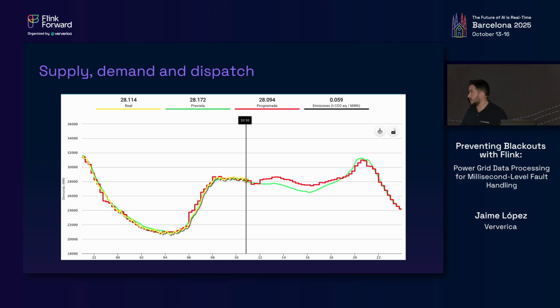When demand spikes, we wake up in the morning, you see it around 6 a.m. This is yesterday's demand in the Spanish grid. People start turning on the coffee maker, people start turning on the lights. Demand starts to ramp up very quickly, especially when work starts in large consumers of electricity, metallurgical plants, manufacturing plants, and suddenly you need to cater to that very quickly. And then at the end of the day, demand goes down, people go to bed, and you have to ramp down and take electricity away from the grid also very quickly.